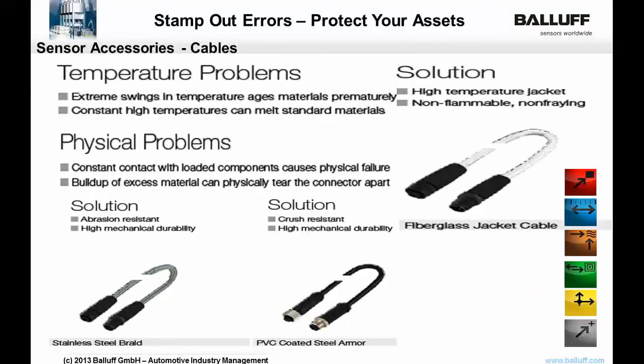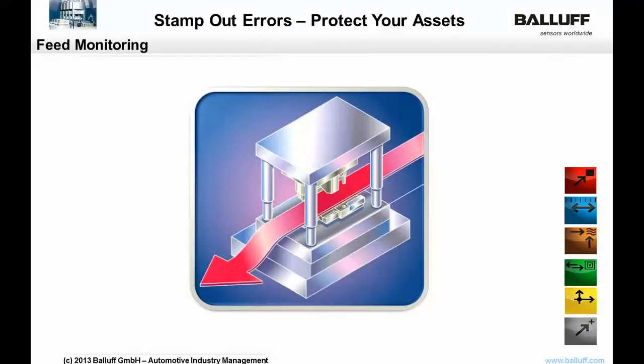So if we looked at harsh duty cables, the primary cables that you may consider are the stainless steel braid, which is perfect for areas where you may have abrasion on the body of the cord set. There's also our PVC steel armor cable that's crush resistant. For those environments where the tooling gets extremely hot, our fiberglass jacket cable would be a good candidate. That's able to withstand up to 400 degrees Celsius. So let's look at a few feed monitoring applications.